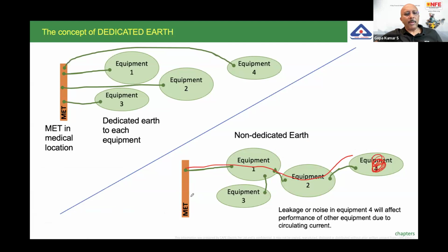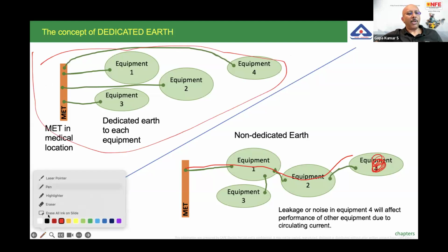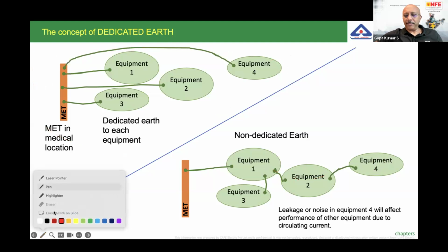So a problem in equipment number 4 is disturbing the performance of equipment number 1 and 2. As a result, the manufacturers most of the time prefer, depending on the type of manufacturer and type of equipment, if it is an electronic equipment and the microprocessor is referenced to the body, to the common protective terminal of the equipment, then of course the manufacturer will ask for an individually earthed system, because he doesn't want any circulating currents on the body of his equipment.